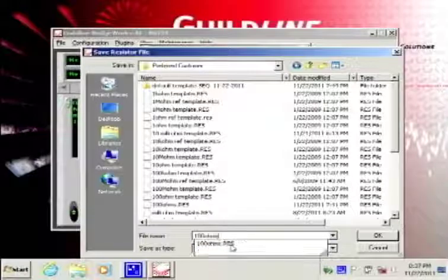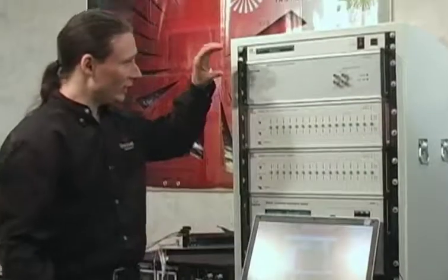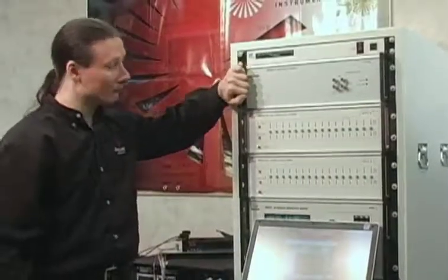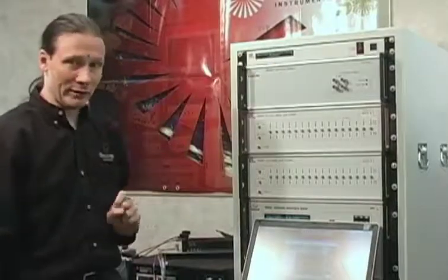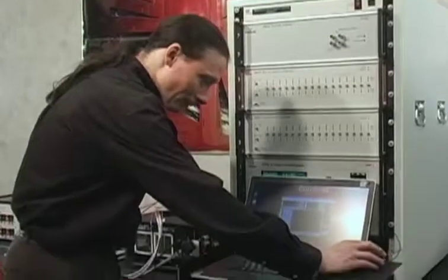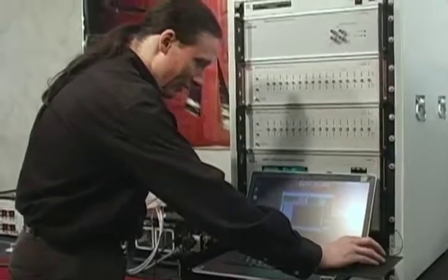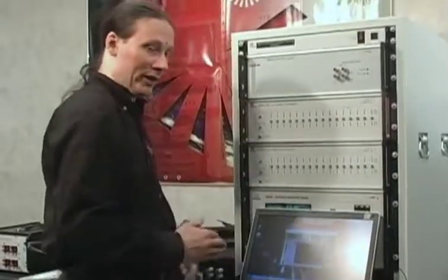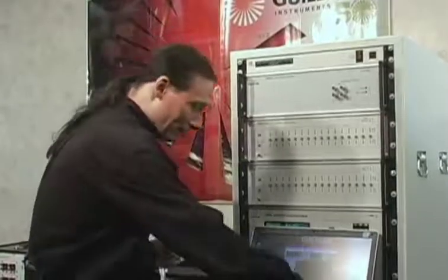Okay. And so you would continue to do that for all the resistors that are up here in your working standards, and you'd have the, of course, known traceable value placed there. When that is complete, then you'll never have to enter that information again until you get new values for the standard.